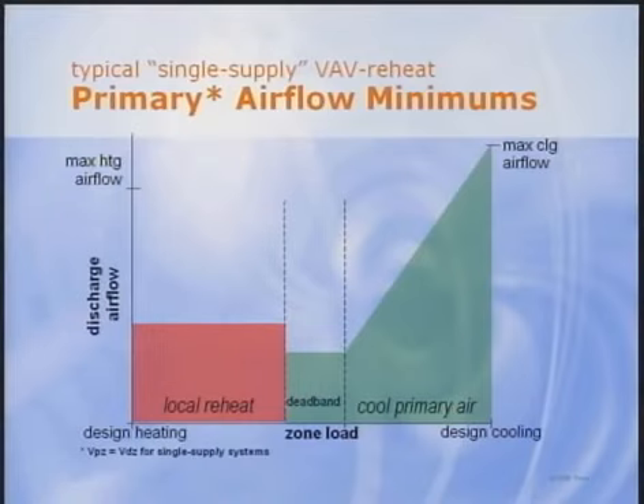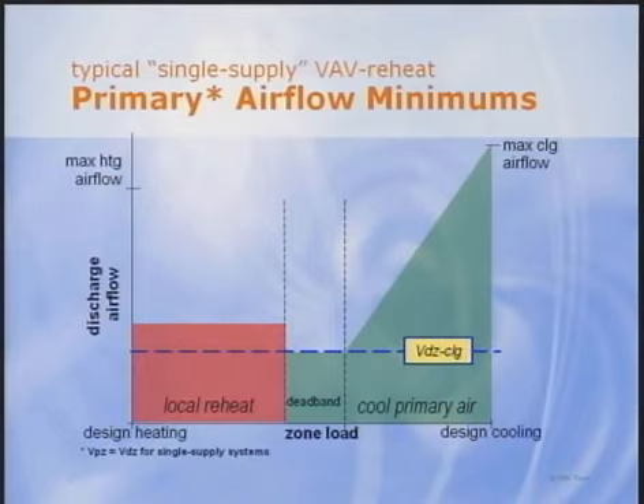Okay, for most designers, the hard part is the 4th step, because you need to know the minimum expected primary airflow for each zone at the condition analyzed. What is it? Is it the minimum zone outdoor airflow needed to comply with Standard 62? Or is it the reheat minimum setting established by Standard 90.1? Or is it some other value? Here's a plot of discharge airflow versus load for a typical VAV zone. As zone cooling load decreases from design, discharge airflow drops until it reaches the cooling minimum setting established by the designer. This setting might be based on sensor or diffuser performance or some other rationale.